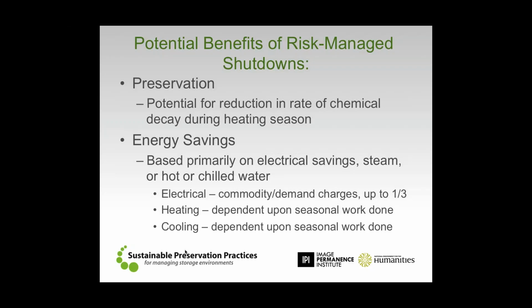There's arguably no better way to save energy than to just turn the entire mechanical system off. And if we can do that for 8 hours a day, or roughly 1/3 of the day, then we can oftentimes save, and we've seen numbers that vary from site to site, but in most cases you save at least 25% on a shutdown, and oftentimes you're looking at somewhere between 30 and 40% total annual energy savings with an 8-hour shutdown at night.